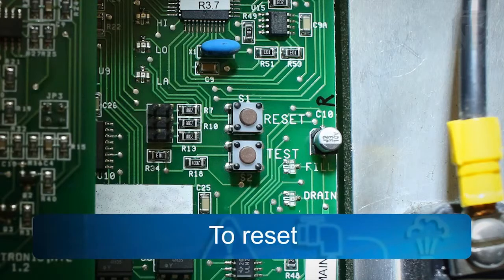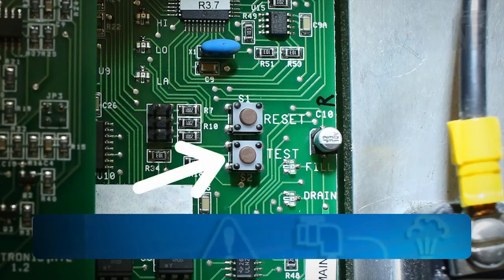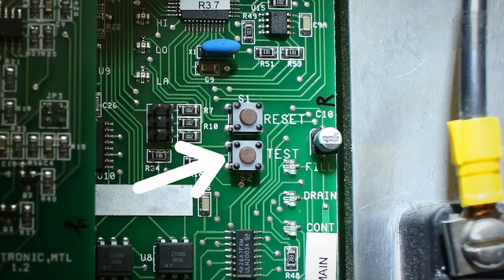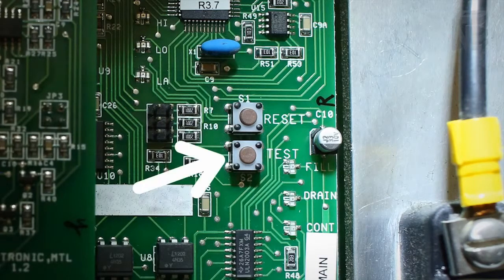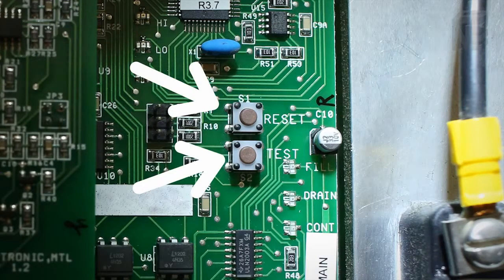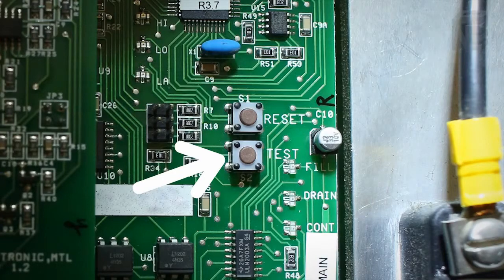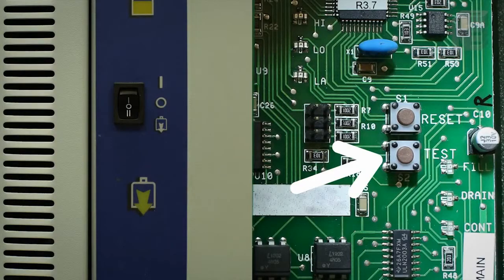To reset the unit after servicing, first press the test button on the main PC board, followed by the reset button. In that order. Test, then reset. When you first press the test button, the unit will go to a drain and the drain LED on the front panel will be on. Then press reset button.